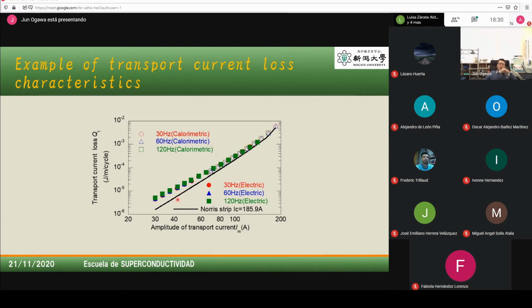For example, a slope of 4 means that going from 20 to 200, the loss increases by an order of 4, meaning 10,000 times. A slope of 3 means a 1,000 times increase. And if we get a slope of 2, it's resistive—meaning the loss is eddy-current dominant. This way we can identify the characteristics of the loss component.